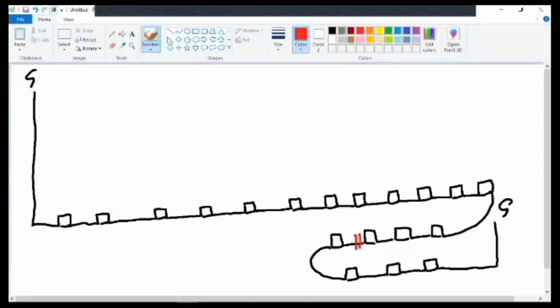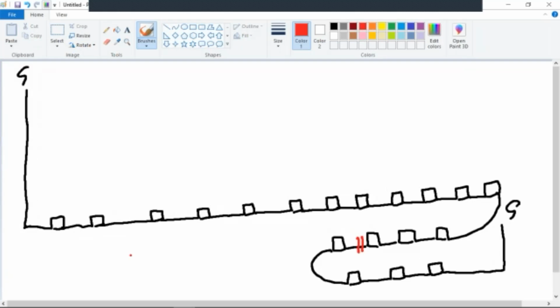Okay, it's back time, so we'll go ahead and get restarted. What I've drawn on here on the board for you guys is a situation. These are certain situations to look out for when you're using fault indicators and in the fault indicator process. Now, you've noticed I've drawn in a bunch of transformers here. And I have a dip at one end and a dip at the other end. And we talked about this when we were out in the field. I've got a normal open point out here in the field. So a couple of things to look out for.